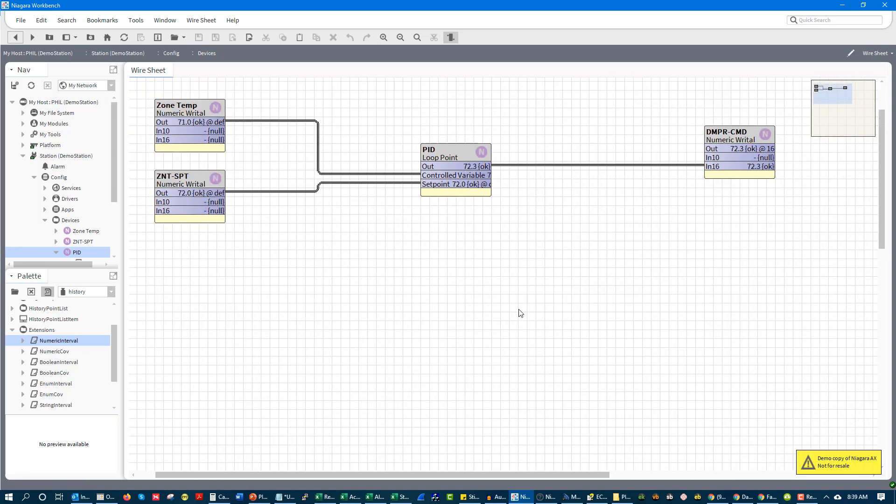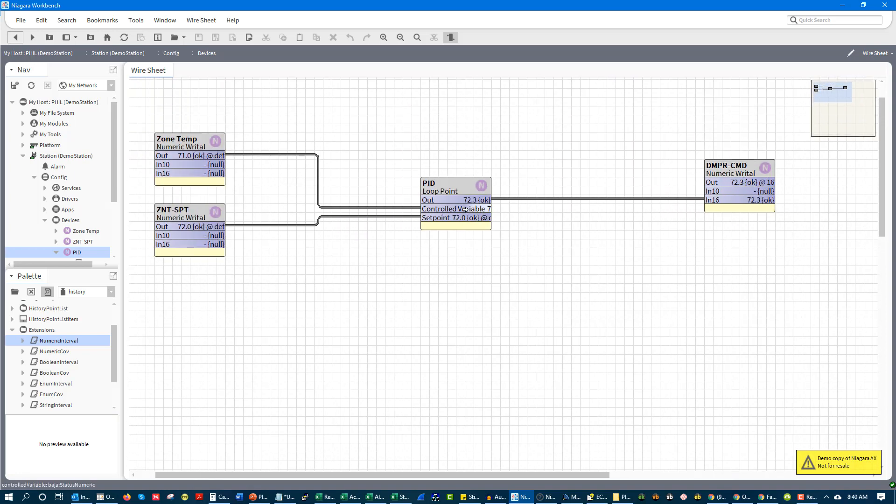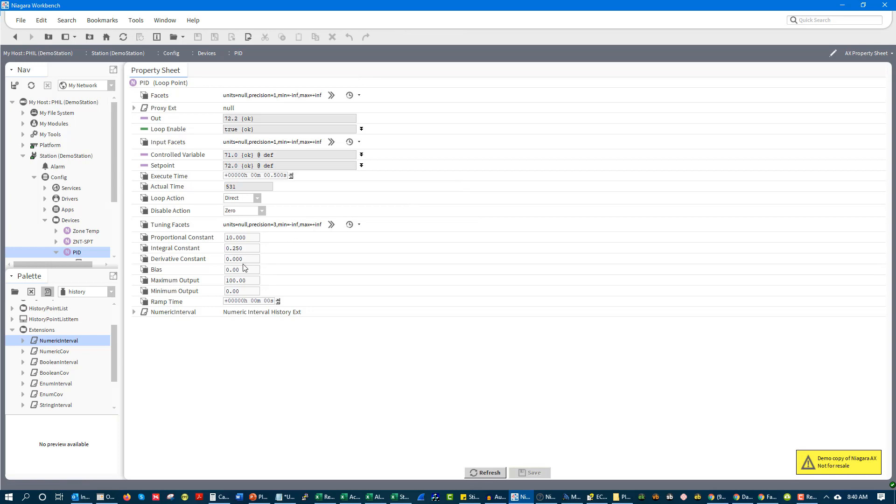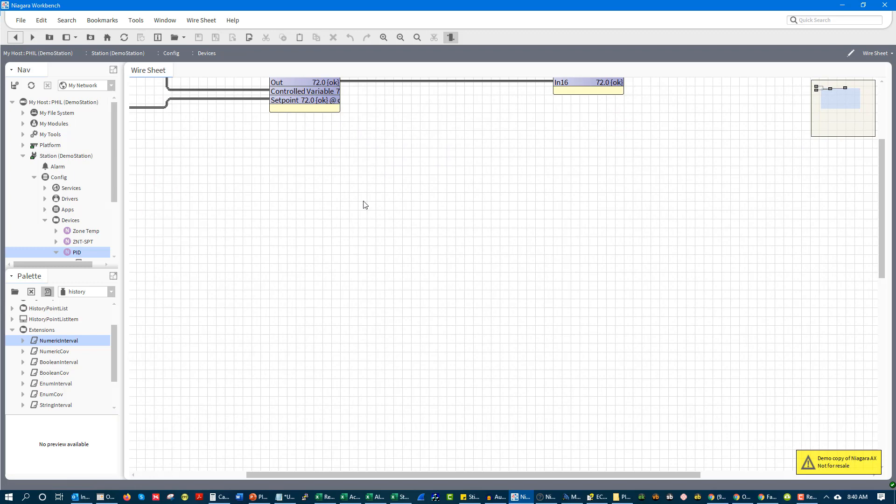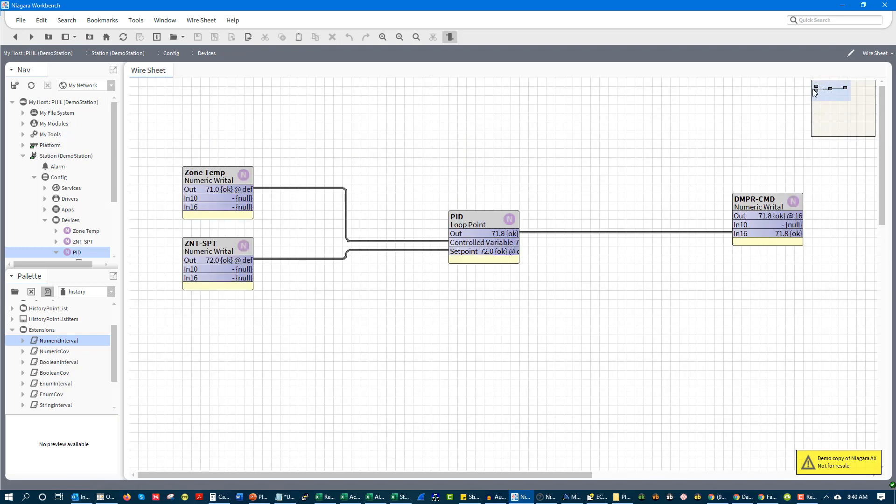You could see that this PID loop is slowly ticking down. I've got a very slow acting loop with a setting at 0.25. And you'll see, I hate that it zooms out every time, but you'll see that integral is causing this to tick down. Because the error is remaining the same.